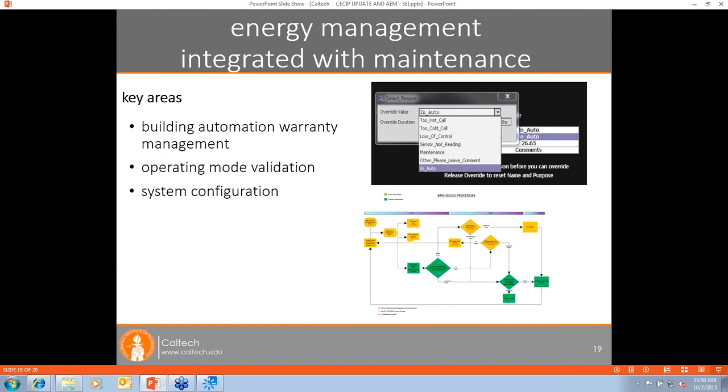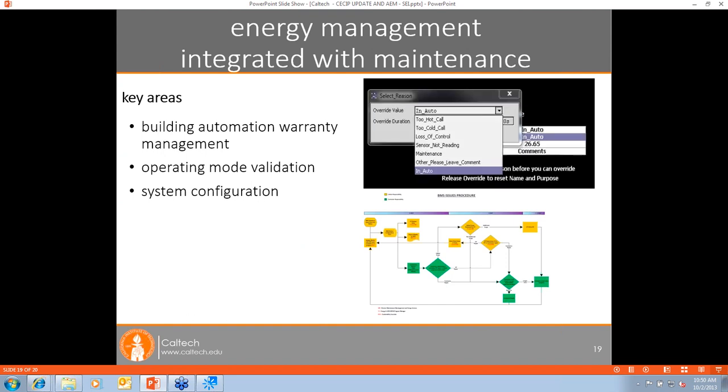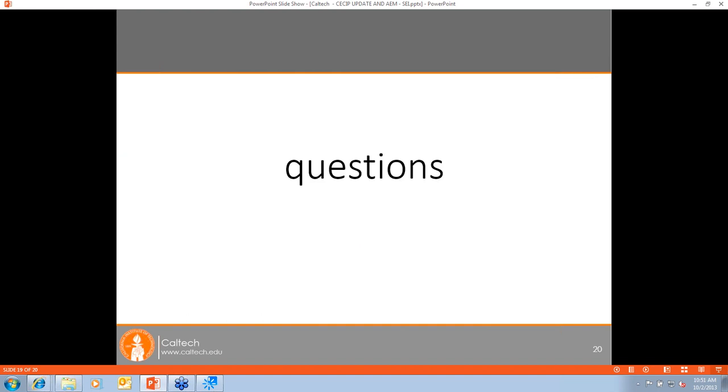We put a whole process in place to track it because operators are responding to things that come up in the field, whether it be a too-hot call or anything else or an airflow issue, and they make the adjustments they think are necessary to make the systems function properly. But if you tie that into the big picture of, hey, there's an ECM that we're relying on a payback for, we're going to try to prove a recordable payback, and these parameters get adjusted, you're going to have trouble. So you're seeing we're approaching this from a very practical operating direction, not just relying on the calculations themselves.